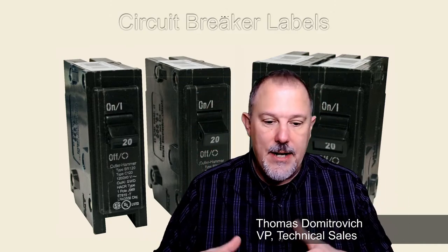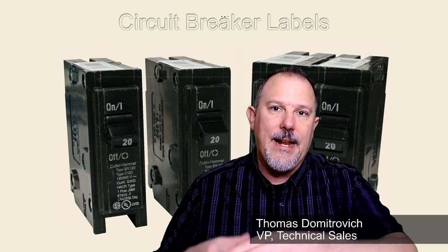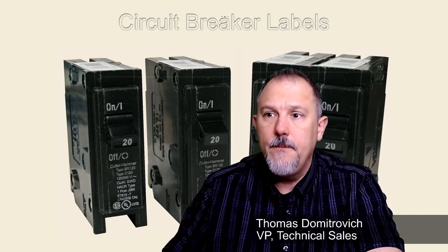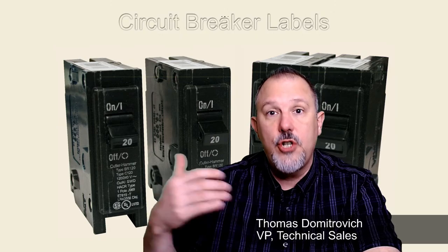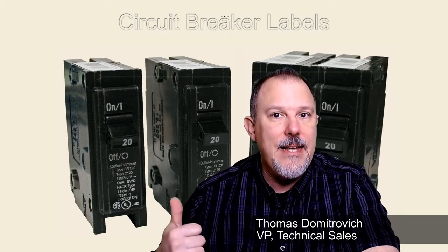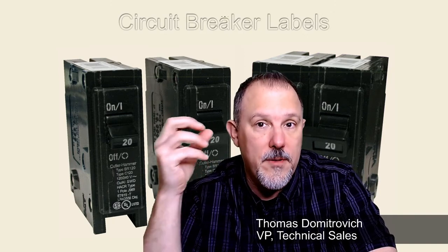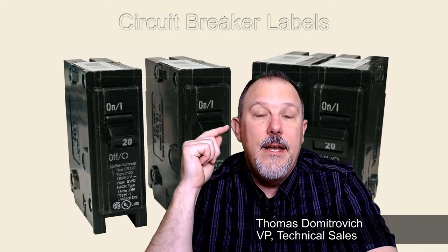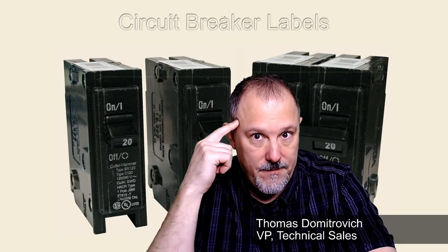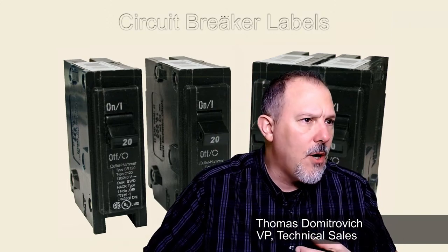It's hard to find. Now, I might find a terminal block that's rated at 90 degrees C, but you're not going to find a fuse switch or a circuit breaker that can handle 90 degrees C conductors used at 90 degrees C ampacity. I can still land a 90 degrees C conductor on this because the 90 degrees C is talking about the insulation that's on a copper or aluminum conductor. I just can't use it at its 90 degrees C ampacity, because then that would make a smaller conductor for the application and I need more copper. So it's about heat, okay? It's all about heat.